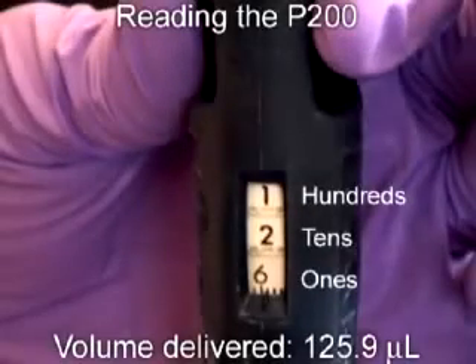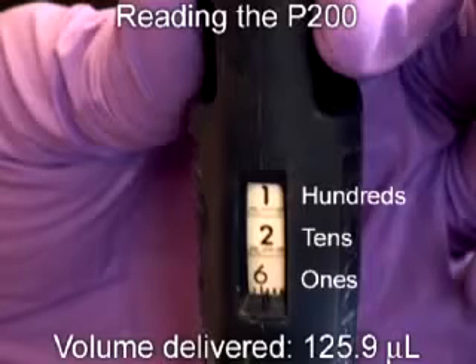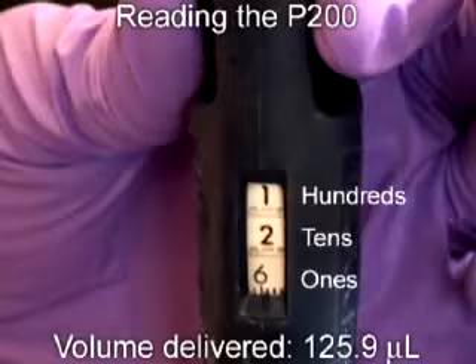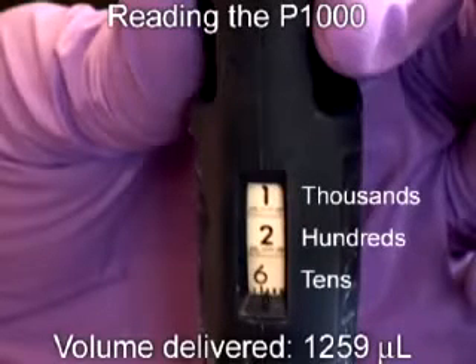After selecting the correct Pipetman and tip, set the desired transfer volume. For the smaller Pipetmen, P2 to P200, the volume set on the indicator translates exactly into the volume that will be delivered. This P200 is set to deliver a volume of 125.9 microliters. For the P1000, the volume set on the indicator must be multiplied by 10 to determine the actual volume that will be transferred.